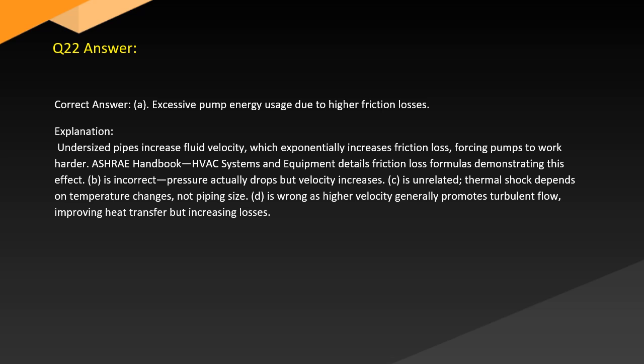Answer. Correct answer: A. Excessive pump energy usage due to higher friction losses. Explanation. Undersized pipes increase fluid velocity, which exponentially increases friction loss, forcing pumps to work harder. The ASHRAE Handbook, HVAC Systems and Equipment, details friction loss formulas demonstrating this effect. B is incorrect. Pressure actually drops, but velocity increases. C is unrelated. Thermal shock depends on temperature changes, not piping size. D is wrong, as higher velocity generally promotes turbulent flow, improving heat transfer but increasing losses.